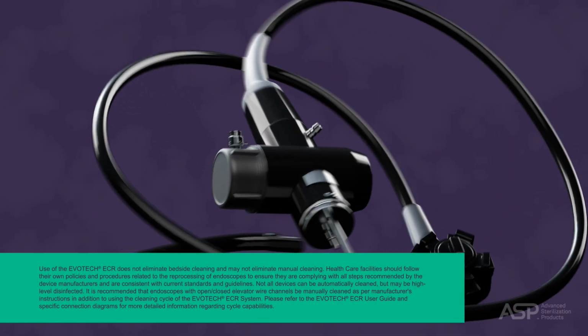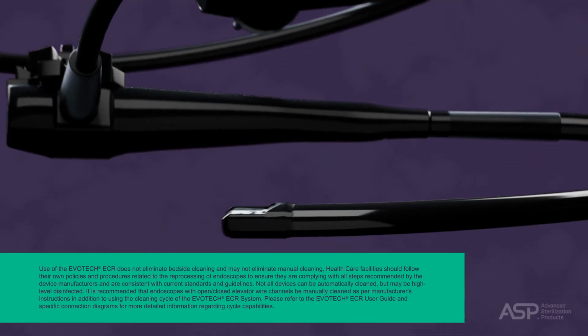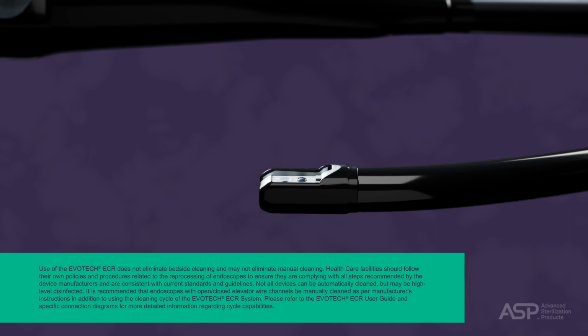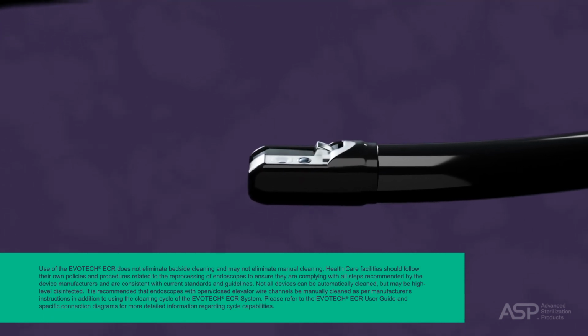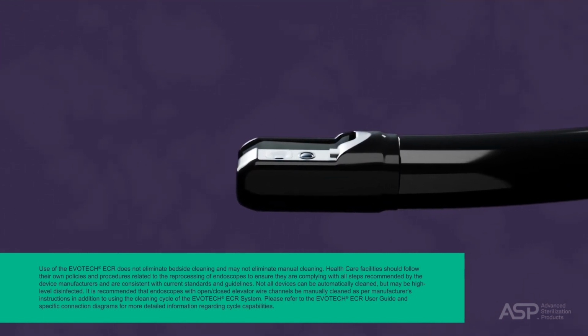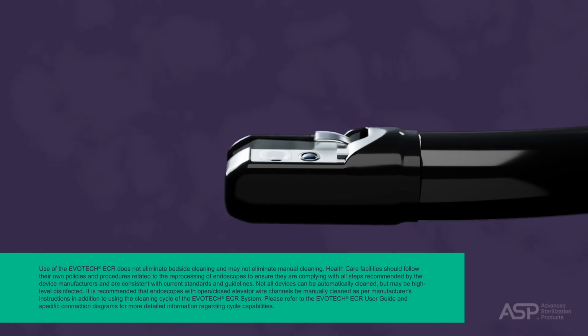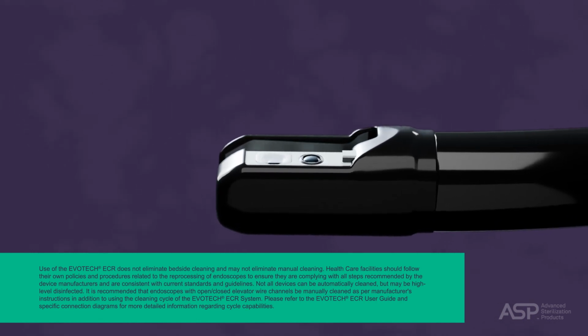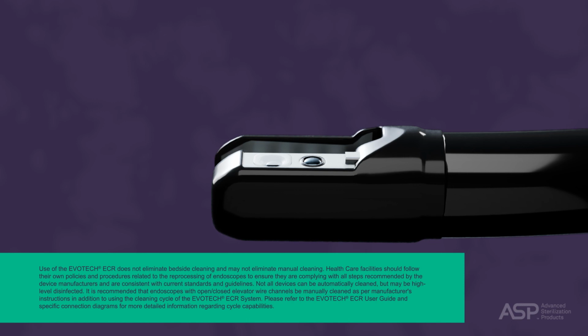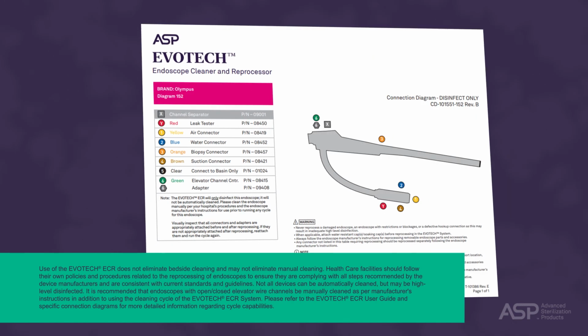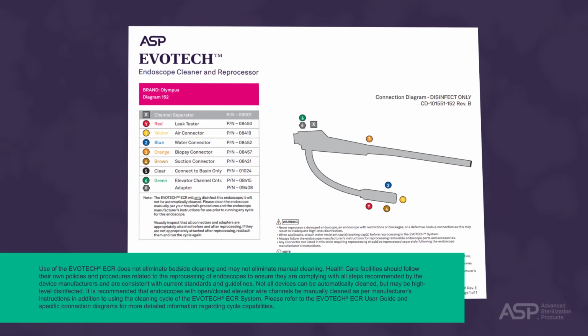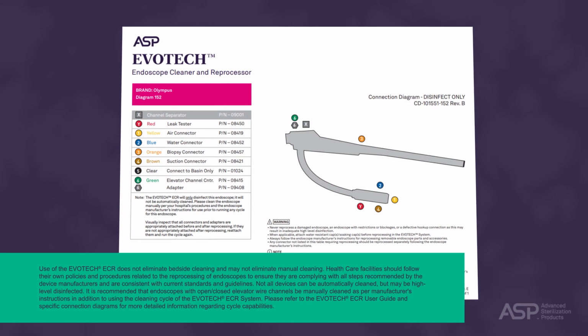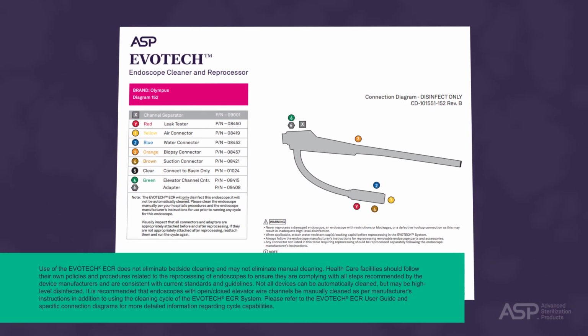Not all devices can be automatically cleaned, but may be high-level disinfected. It is recommended that endoscopes with open-closed elevator wire channels be manually cleaned, as per manufacturer's instructions, in addition to using the cleaning cycle of the EVOTECH ECR system. Please refer to the EVOTECH ECR user guide and specific connection diagrams for more detailed information regarding cycle capabilities.